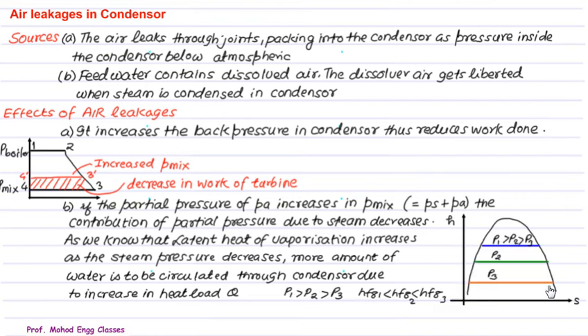This can be seen with the T-s plot also. As seen from this H-s plot or T-s plot, this is the higher pressure, this is the intermediate pressure, and this is the low pressure. This quantity actually represents the H-fg value. As the pressure of the steam goes on decreasing, that will be the net increase in the heat load of the condenser. To satisfy this requirement, we have to supply more quantity of water.